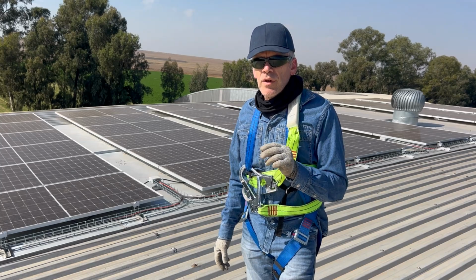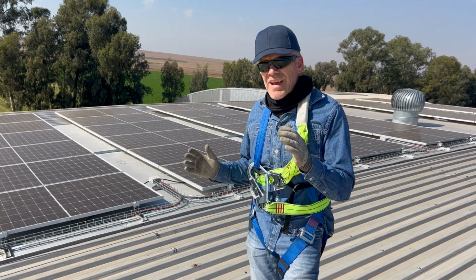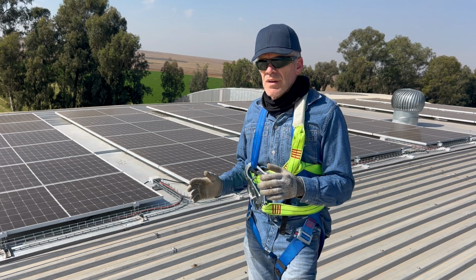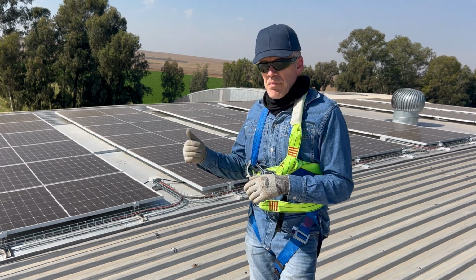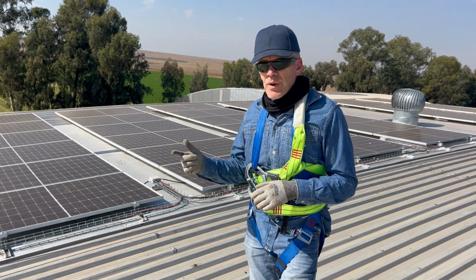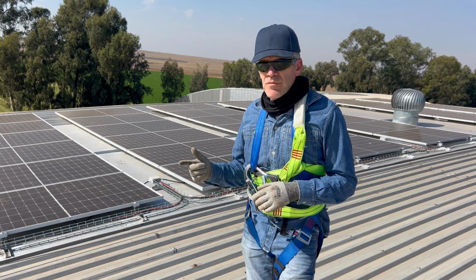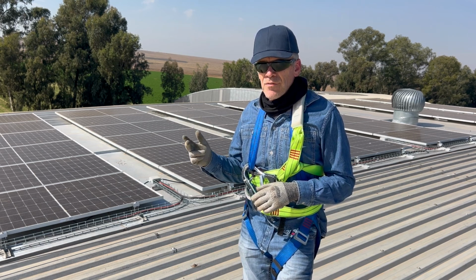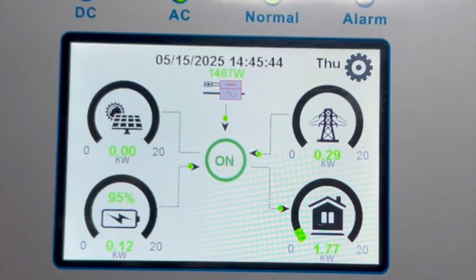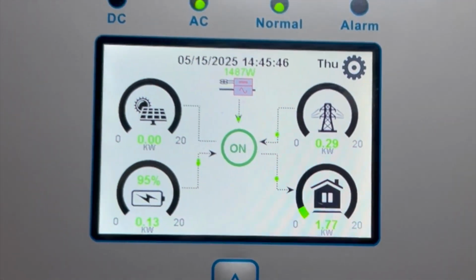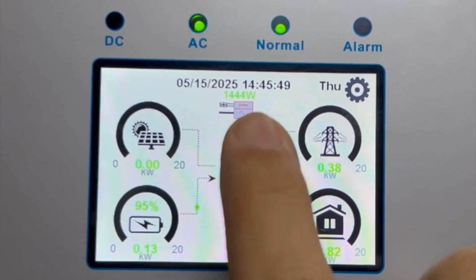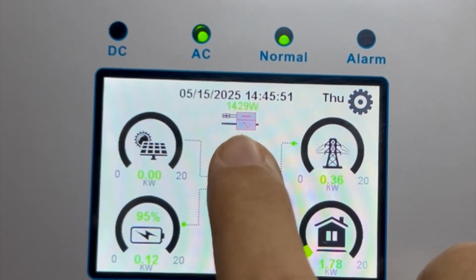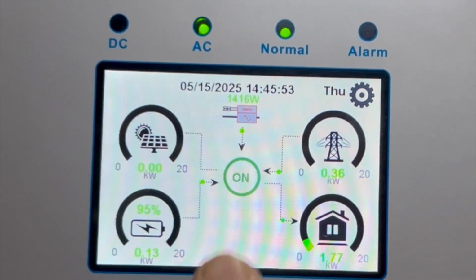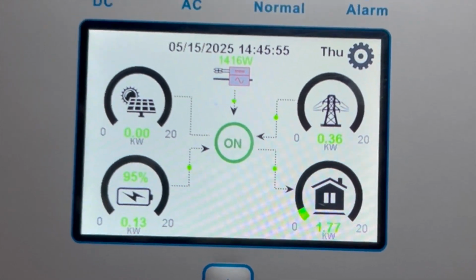In this video, we are going to be taking a look at an AC coupled system that combines microinverters, a 20 kilowatt Deye Hybrid inverter, and a high voltage lithium ion battery bank. This is an AC coupled system, and we've got about 15 kilowatts of solar connected to the inverter on the gen input.